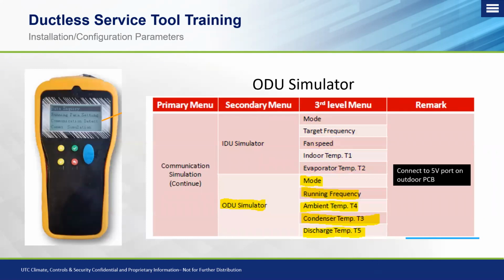Okay, with the outdoor unit simulator, this is going to be done by using that 5-volt DC connection. And again, this is the one where you plug it in on the test port pin, and you can access the mode information, the running frequency of the compressors, target frequency. You can get ambient temperature, outdoor coil temperature, and discharge temperature to verify that those sensors are also reading properly.